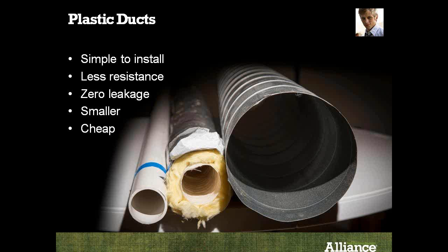Yeah, and so I just want to talk about some of the advantages of plastic duct systems that would be used for this kind of manifold system. Currently, plastic ducts are not allowed according to code, specifically PVC ductwork. But PVC ductwork is something we envision as a great example of how we could use existing building technologies in a new way that perhaps is better than some of the incumbent technologies.